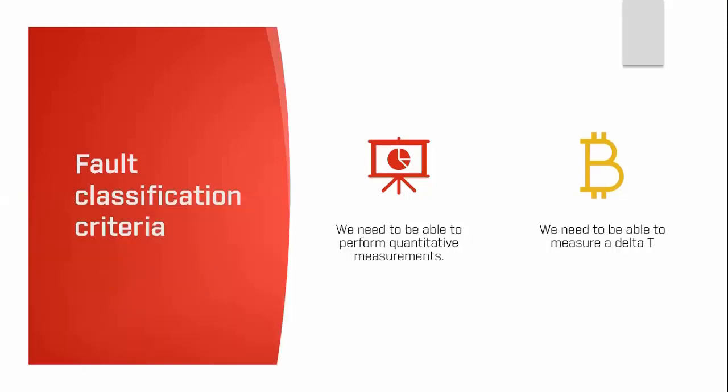To perform fault classification criteria, we need to perform two tasks. First, quantitative measurements — set up the camera with correct emissivity, environment, and surface knowledge to take an accurate temperature measurement. Second, we need to do this twice — either at two points on one component, or between one thermal image and another. That measurement is called a delta T, and all fault classification criteria is based on a delta T measurement.